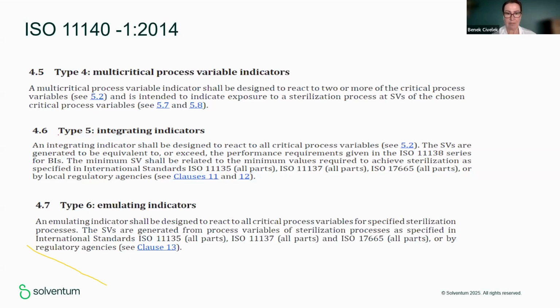When we move to type 5, it has a different explanation here. It says it is reacting to all critical variables, but the stated values should be equivalent to or exceed the performance of a biological indicator. So why does it tell about this? It doesn't mean that a type 5 will replace a biological indicator, but it means that the stated values, I mean the pass-fail threshold values of a type 5, are tested under as challenging conditions as a biological indicator.